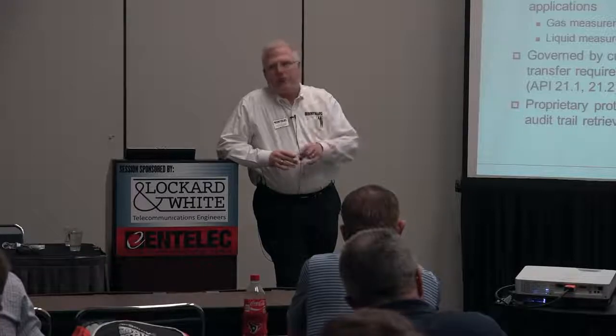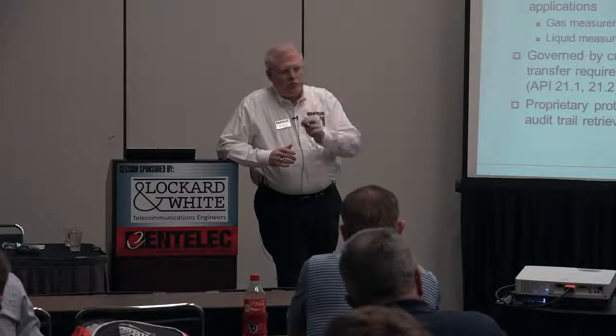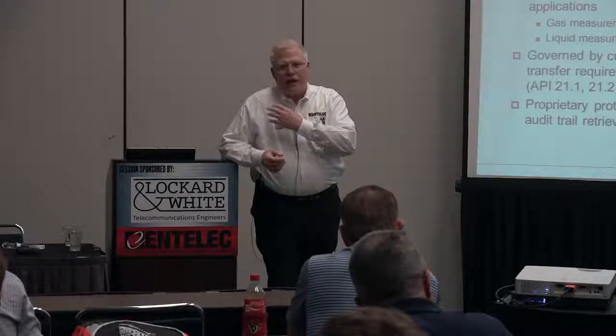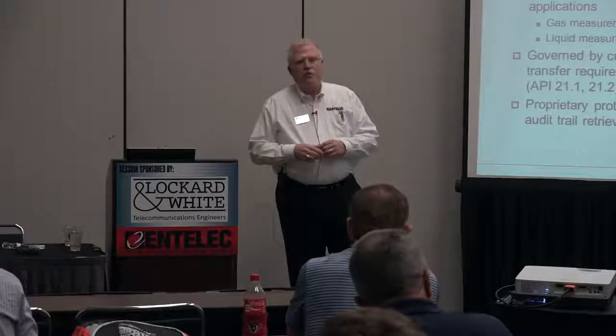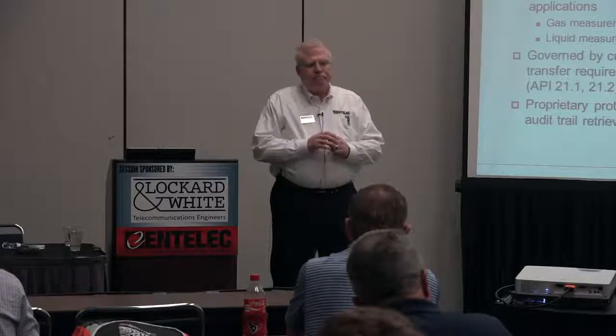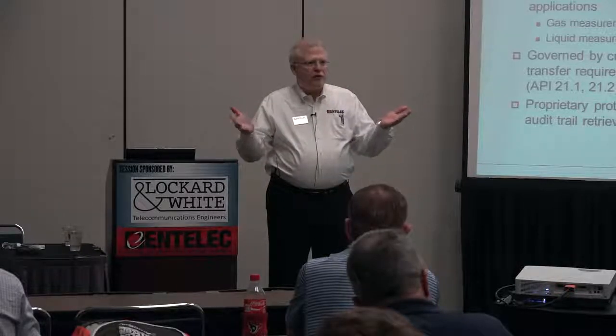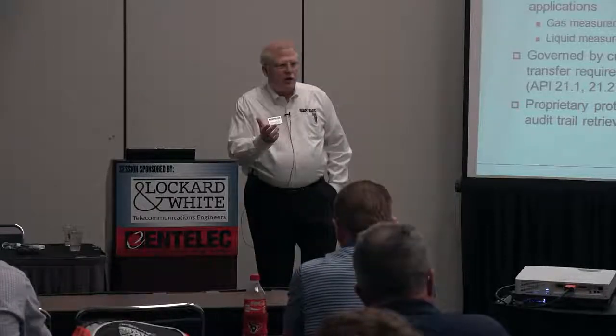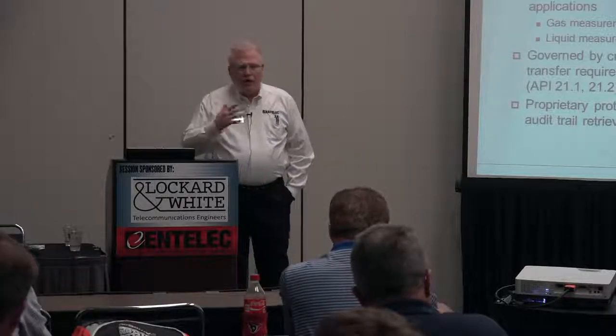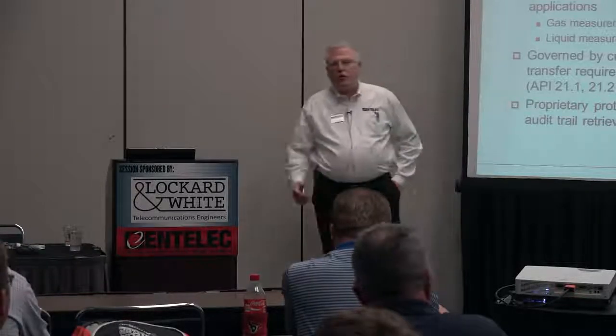EFM stands for electronic flow meter. An electronic flow meter is a specialized RTU — it does flow measurement, and there are liquid EFM and gas EFM. Like RTUs, they're purpose-built and designed to be low power, but they do custody transfer measurement. Custody transfer means the ownership of the product is changing hands, which means it's subject to audit. It falls under Sarbanes-Oxley and is governed by specifications from the American Petroleum Institute.